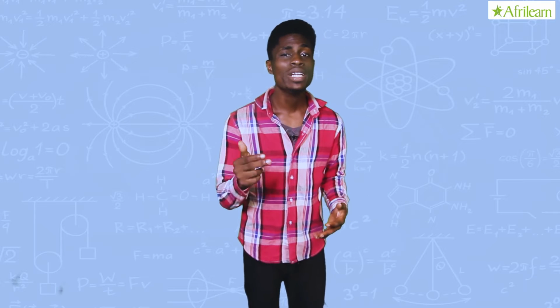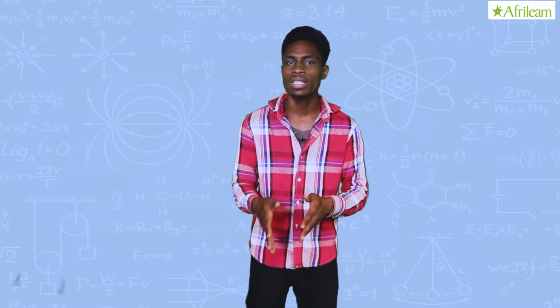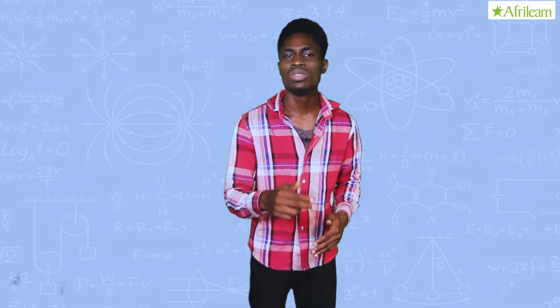However, when fully charged, the cell develops an EMF of about 2 volts, but as it is discharged, the EMF decreases slowly to about 1.8 volts. If the cell is allowed to discharge completely, its voltage finally falls off very rapidly.